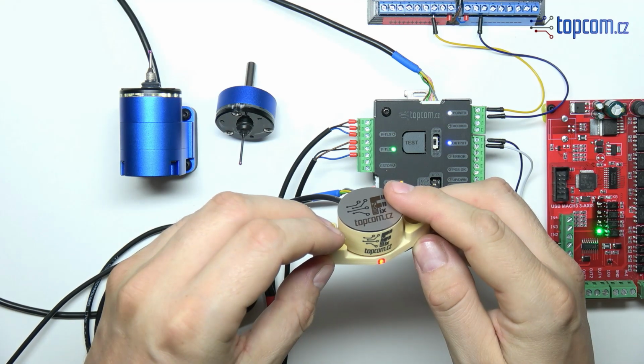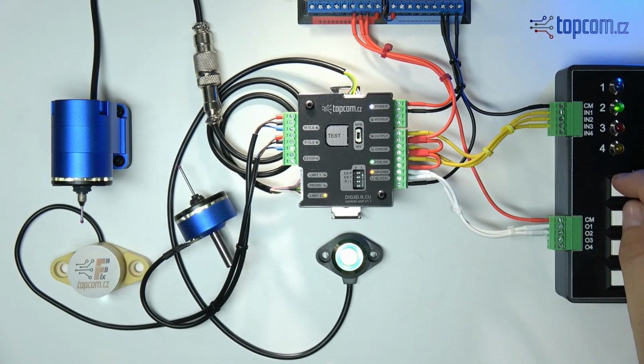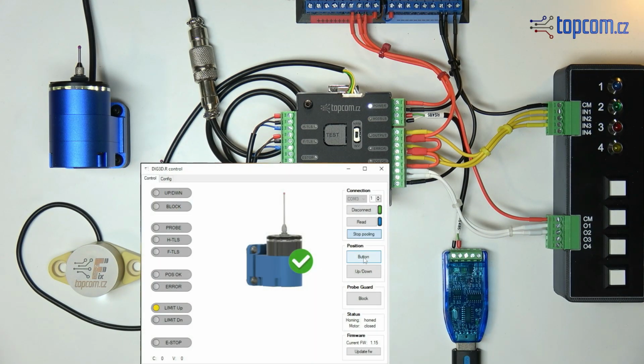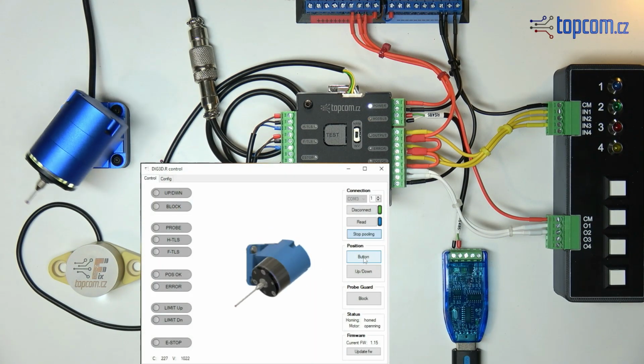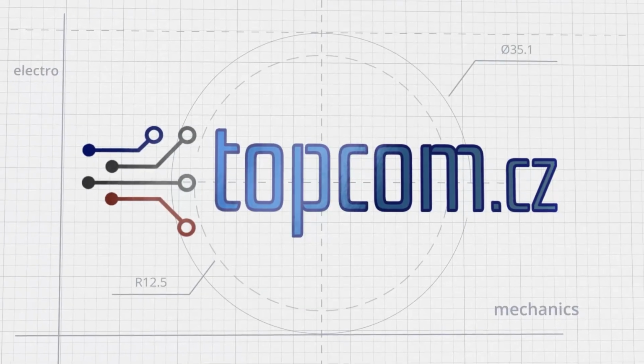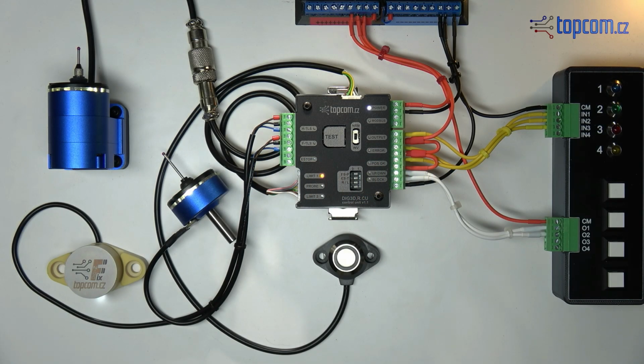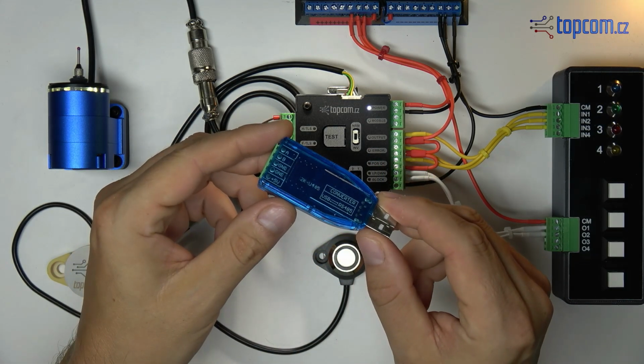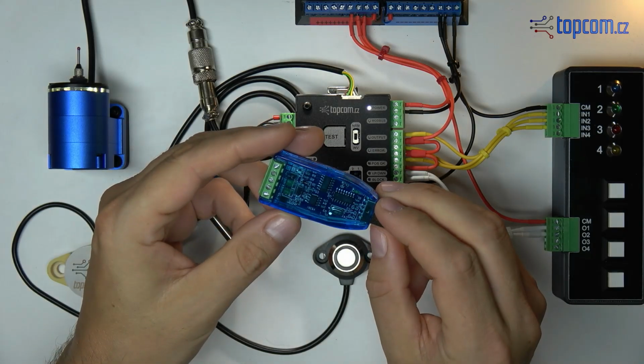In the previous episodes we learned how to set up the rotary probe and connect it to any motion controller. Today we'll show you how the rotary probe can be controlled and configured via the Modbus directly from your computer. Communication with the probe's control unit is handled via the RS-485 bus using the Modbus protocol.